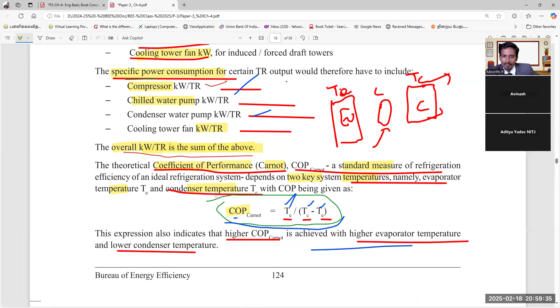How to do the COP? Coefficient of performance - what is the performance? How is this performance done? We have to measure it. Who does the cooling effect - compressor or evaporator? Evaporator, right? Always remember evaporator. So the evaporator does the cooling effect. What is the input they are giving? Compressor power, sir. Yes, compressor power - always remember. So COP means the cooling effect divided by compressor input.